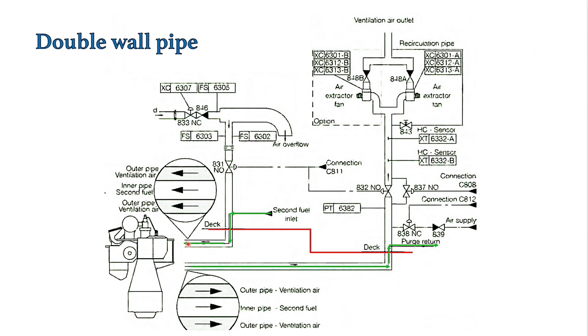Now when this double wall piping is connected to the main engine, it will be connected with the help of O-rings, and as we all know that O-rings are not 100% leak proof. So there may be minute leaks. For that purpose a ventilation system is provided so that it is continuously ventilated. This outer section is continuously ventilated. Keep in mind that this double wall piping system is fully incorporated into the main engine — all components necessary for dual fuel mode operation will have a provision for this double wall piping.